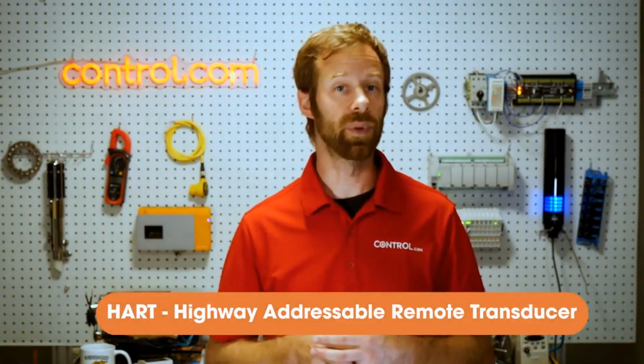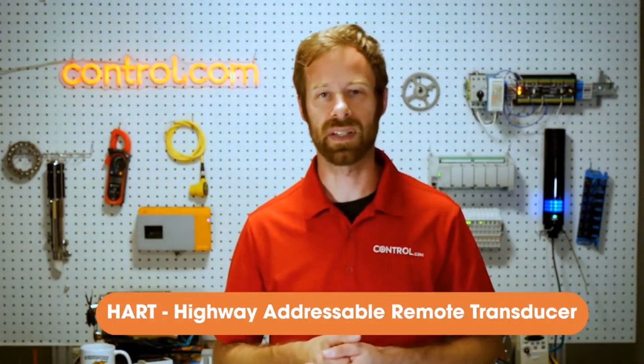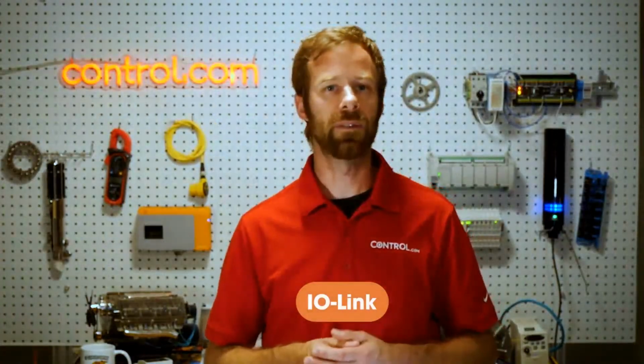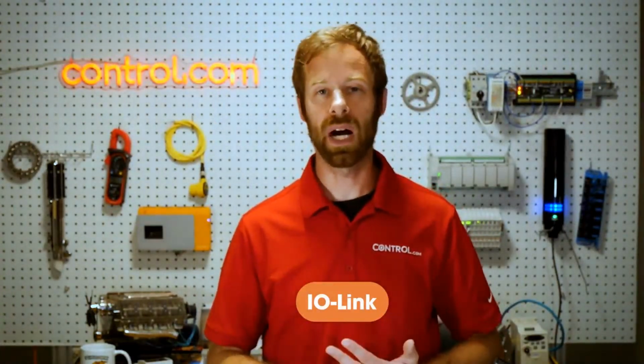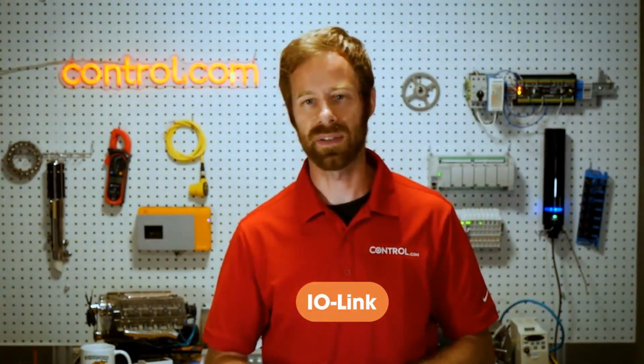The two most common standouts in this area are a couple of protocols. One is slightly older and it's called HART, Highway Addressable Remote Transducer. We'll talk about this in a second. And also IO-Link. IO-Link is one that has been around for a little while, but is becoming extremely popular in connecting all kinds of different devices.